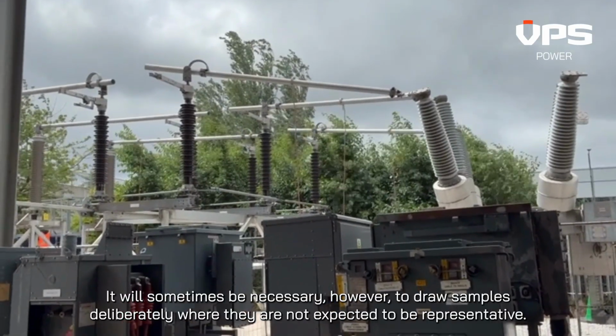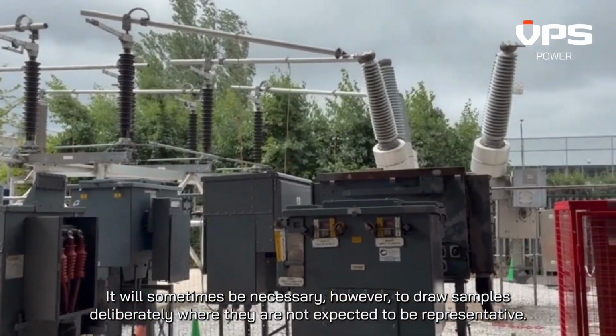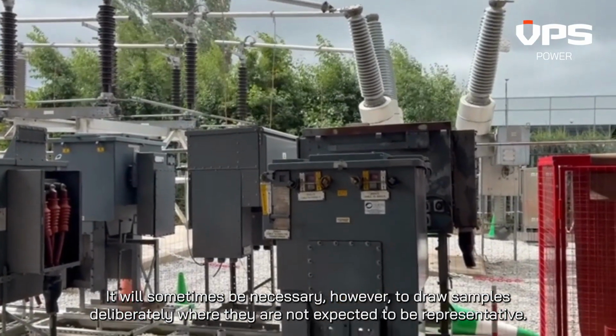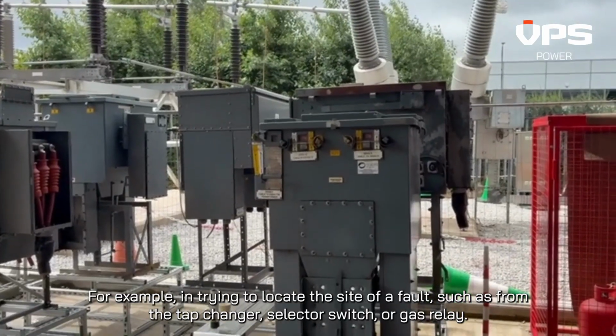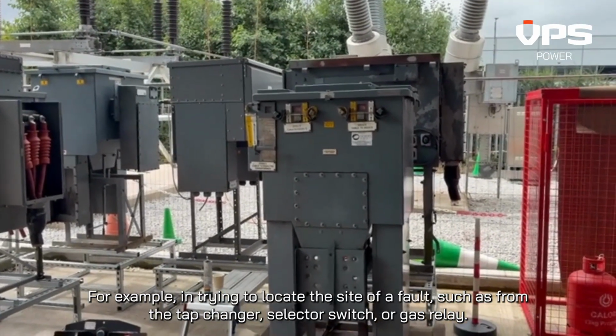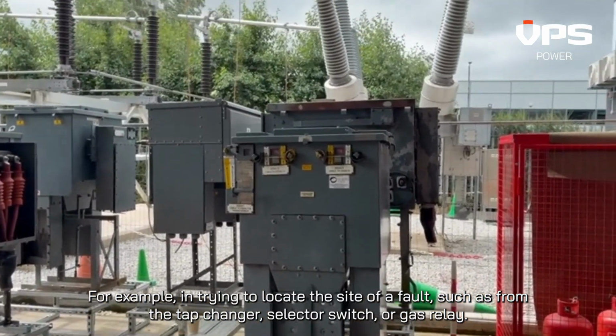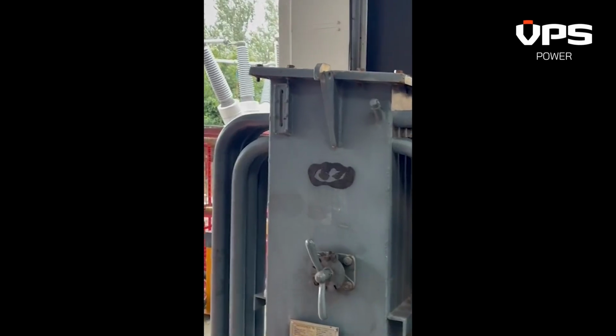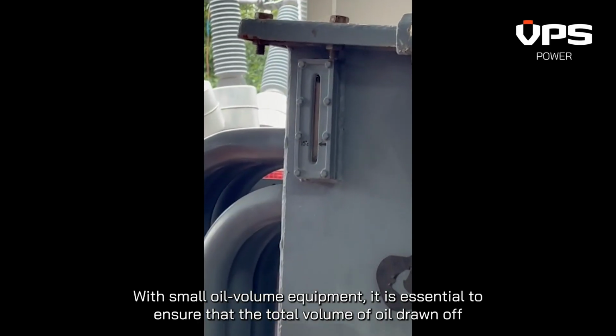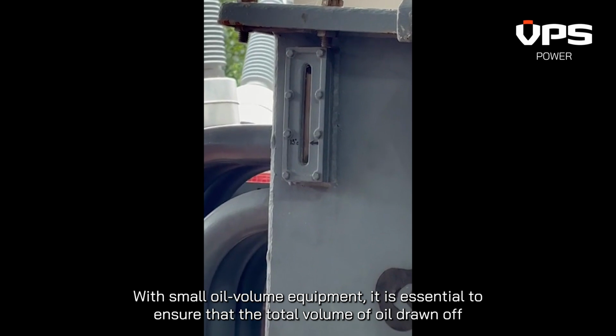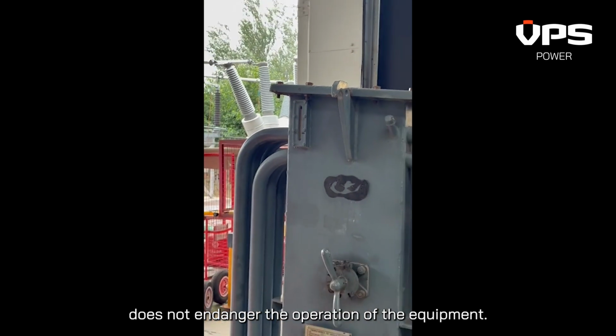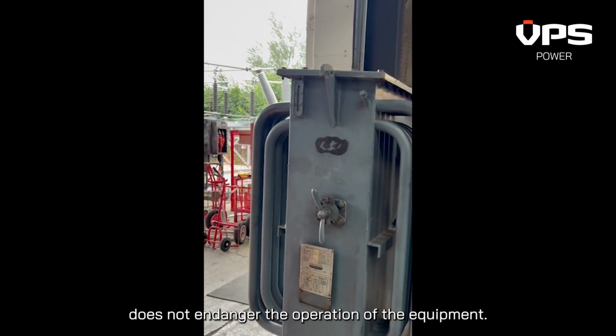It will sometimes be necessary, however, to draw samples deliberately where they are not expected to be representative, for example in trying to locate the site of a fault, such as from the tap changer, selector switch or gas relay. With small oil volume equipment, it is essential to ensure that the total volume of oil drawn off does not endanger the operation of the equipment.